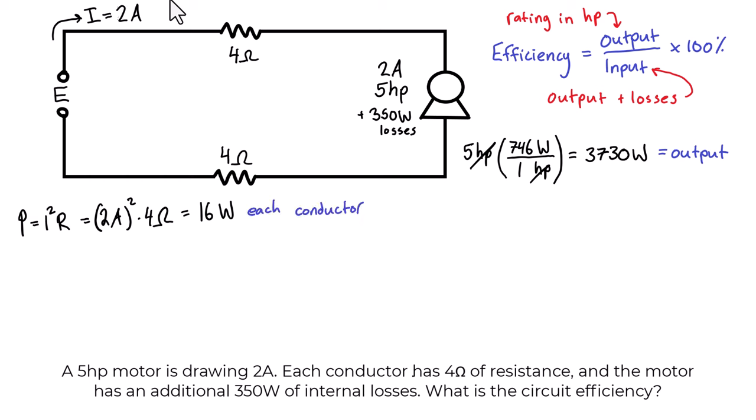So let's just lay out our output, losses, and input here. So our output we've already calculated, it's 3730 watts. Now our losses was the 350 from the motor itself plus 16 watts for the first conductor plus another 16 watts for the second conductor. And we're going to get a total amount of losses in this circuit at 382 watts in total. Then our input is going to be equal to our output plus our losses. So that's going to be 3730 watts plus 382 watts. So our total input to the circuit is going to be 4112 watts.